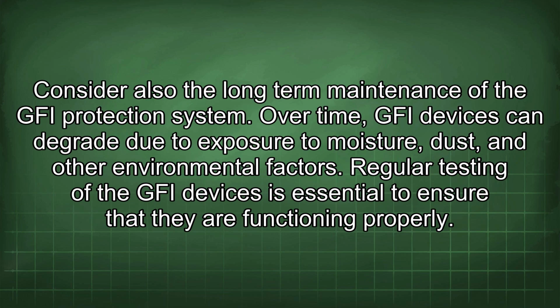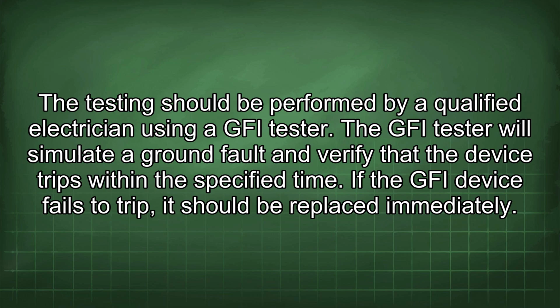Consider also the long-term maintenance of the GFI protection system. Over time, GFI devices can degrade due to exposure to moisture, dust, and other environmental factors. Regular testing of the GFI devices is essential to ensure that they are functioning properly. The testing should be performed by a qualified electrician using a GFI tester. The GFI tester will simulate a ground fault and verify that the device trips within the specified time. If the GFI device fails to trip, it should be replaced immediately.